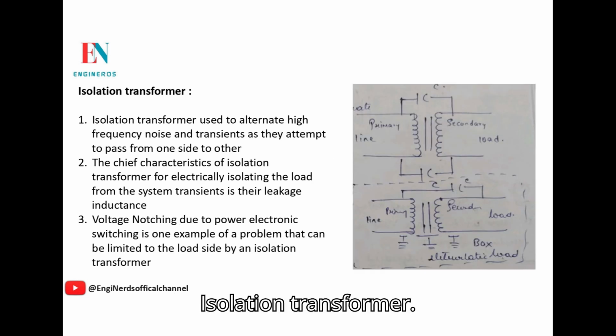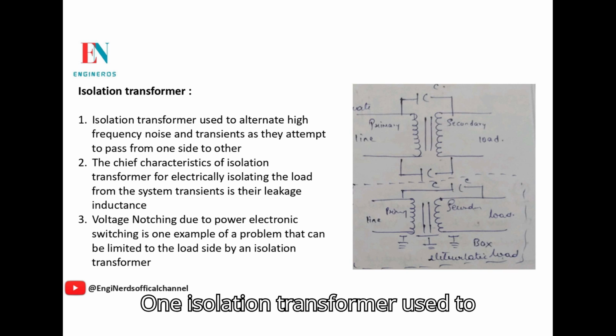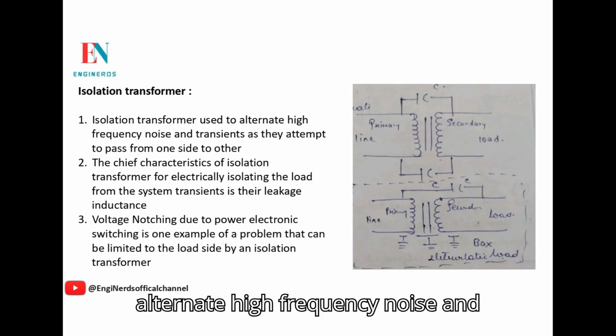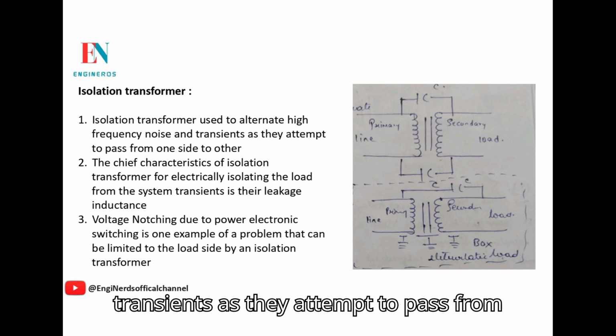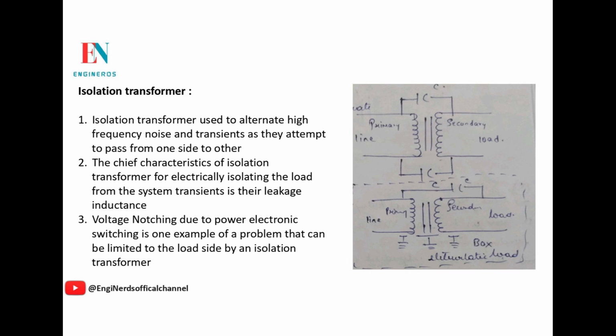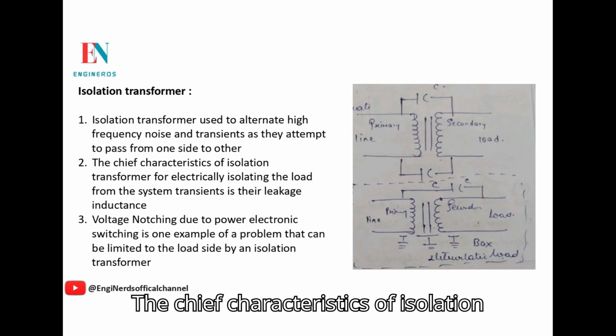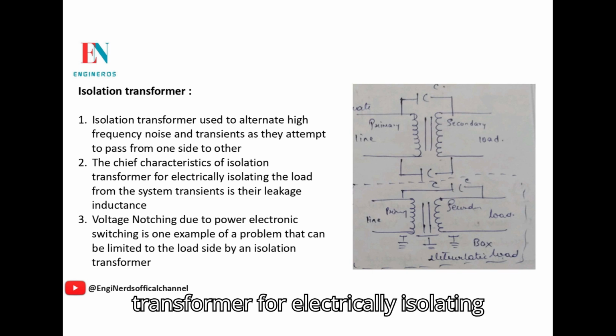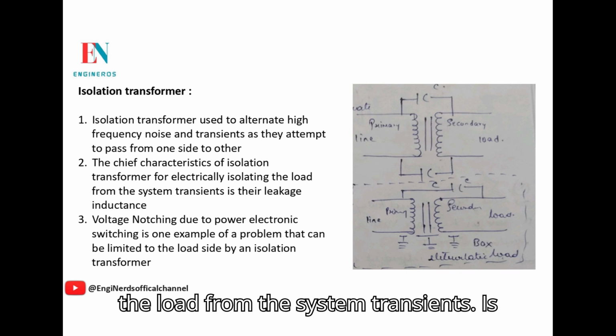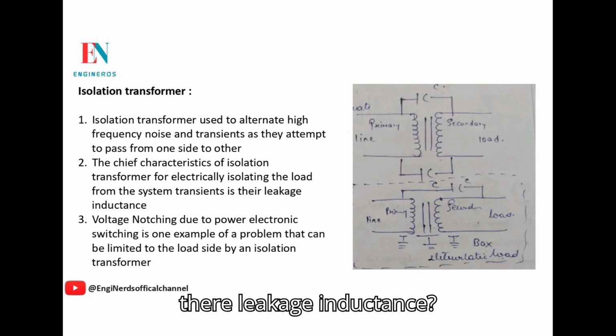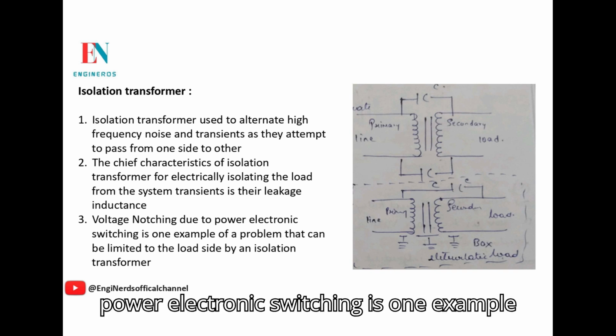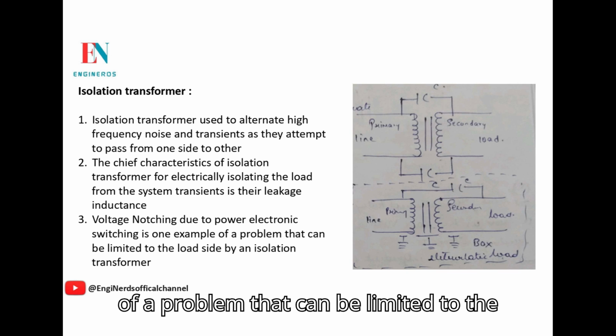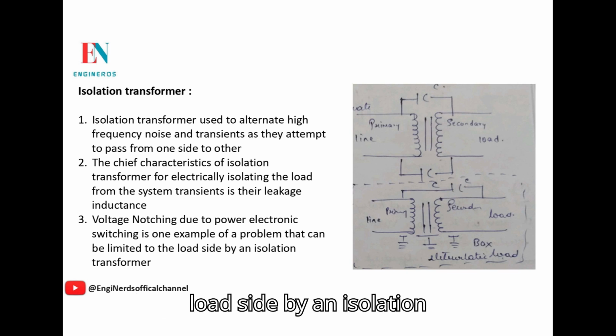Isolation transformer. 1. Isolation transformers are used to attenuate high-frequency noise and transients as they attempt to pass from one side to the other. 2. The chief characteristic of an isolation transformer for electrically isolating the load from system transients is its leakage inductance. 3. Voltage notching due to power electronic switching is one example of a problem that can be limited to the load side by an isolation transformer.